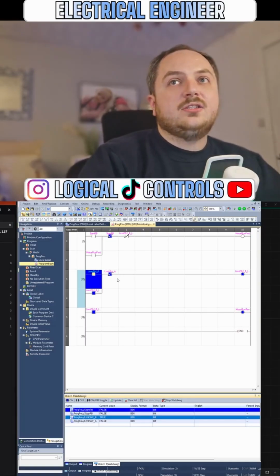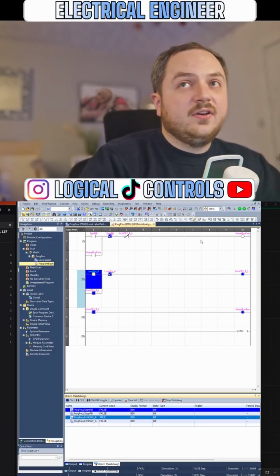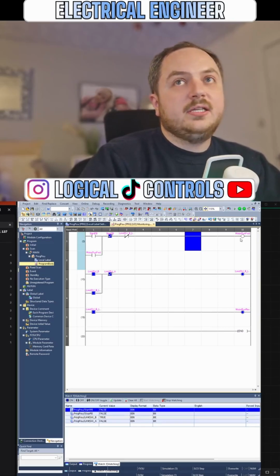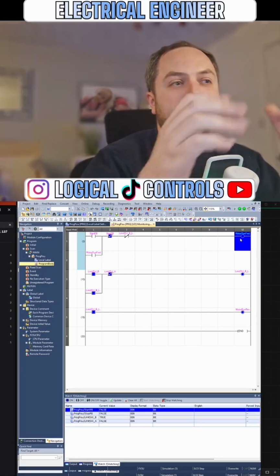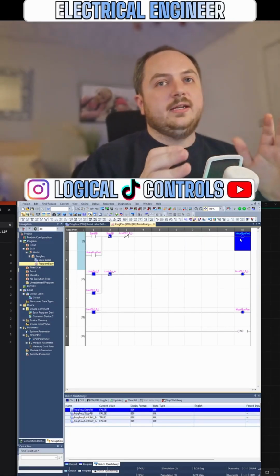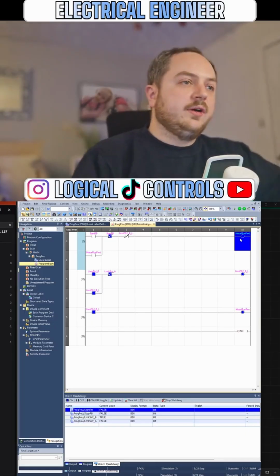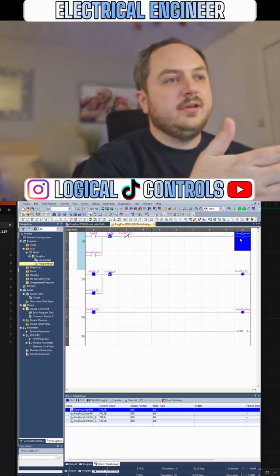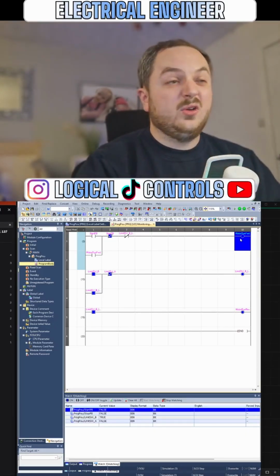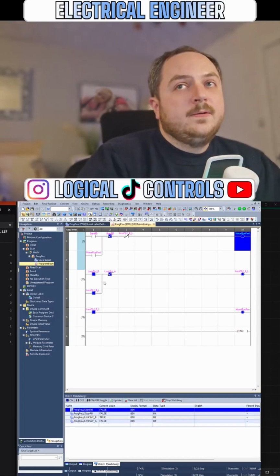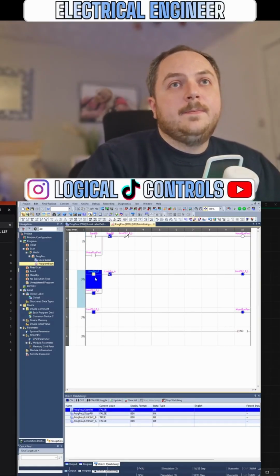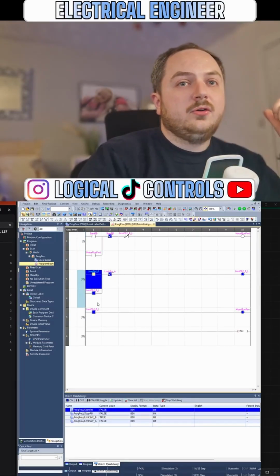So why has the motor gone in reverse? Again, this is very quick - I'd have to think a bit more about this if I sat down properly. You'd maybe want some delay between the motor running forward and the motor getting slammed in reverse. You'd want a period where you haven't got any power on the motor, or you've got a brake on or something. But just for this, we've hit limit switch B and the motor's slung in reverse.